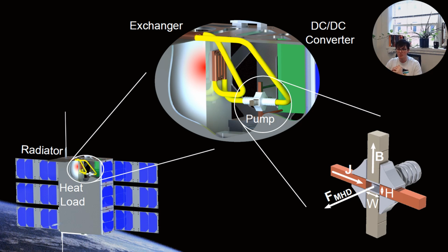So what our lab is proposing here is a magnetohydrodynamically pumped cooling loop. Now, this is just like a mechanically pumped fluid loop, except we replace that mechanical pump with one that runs on the Lorentz force. What happens here is we build a pump body where liquid metal is able to run through it. We put copper conductors on either side of that pump body that run a DC electrical current through the liquid metal. Perpendicular to those, we place two sets of permanent neodymium magnets which generate a strong magnetic field in that pump cross-section. So now you have an electrical current crossed with a magnetic field, which gets you a Lorentz force, and that is how we actually pump the fluid through the loop.